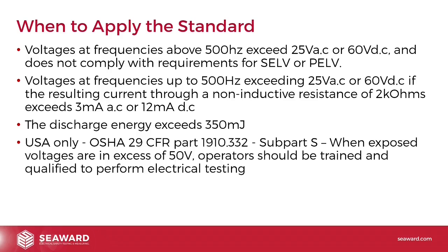We also apply the standard at voltages at frequencies up to 500 Hz exceeding 25 volts AC or 60 volts DC if the resulting current through a non-inductive resistance of 2 kiloohms exceeds 3 milliamps AC or 12 milliamps DC. So you can see that the limits we're talking about, 5 milliamps and that kind of thing, are higher than that, so we need to apply this standard. Or if the discharge of energy exceeds 350 millijoules.